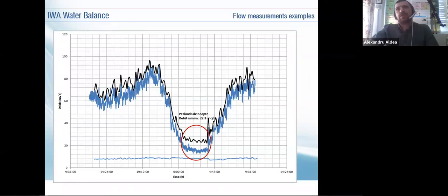So we took measurements of the wells, and in one of them we found this particular pattern here. After some inquiry, we found out that that particular well didn't go into the reservoir, but directly into the network. So this is how we found out that you have raw water in the network. A little bit of detective work, if you will.